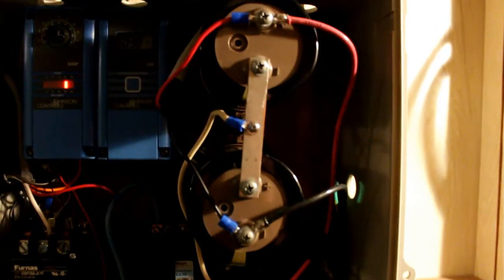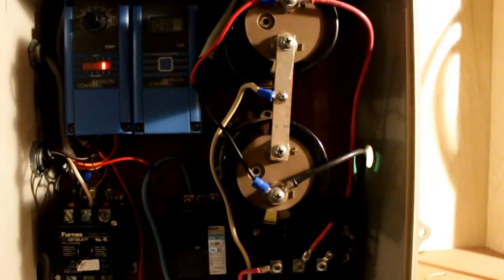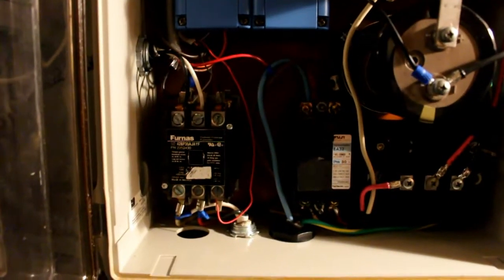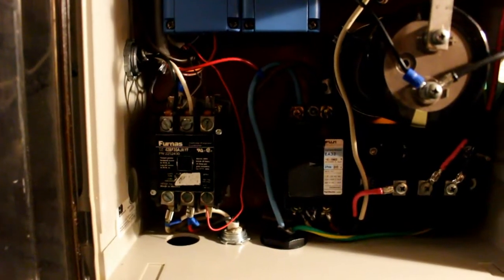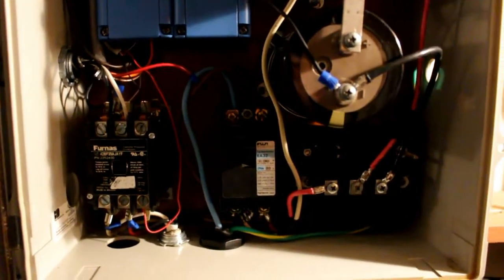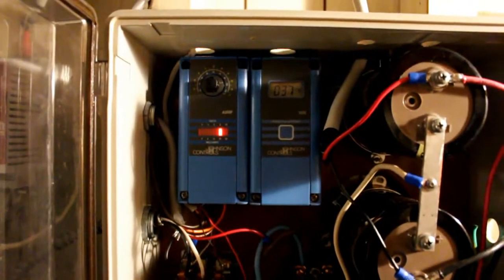That half bridge rectifier and those two capacitors are the voltage doubler. And there's the contactor that tells the motor controller to start and runs the condenser fan, circuit breaker, and temperature controller.